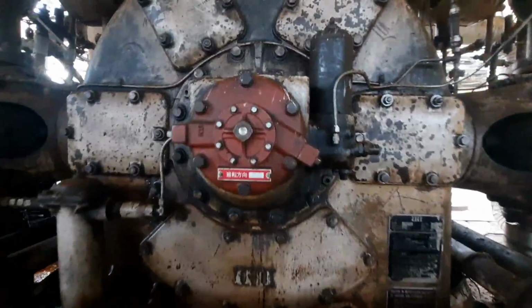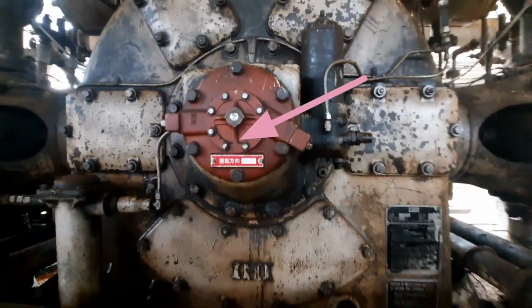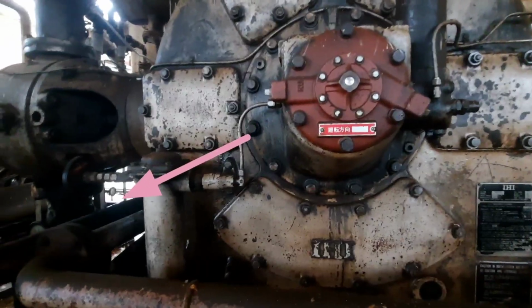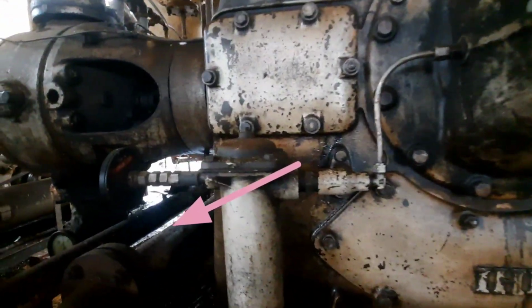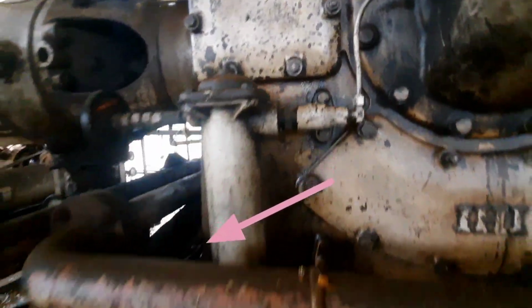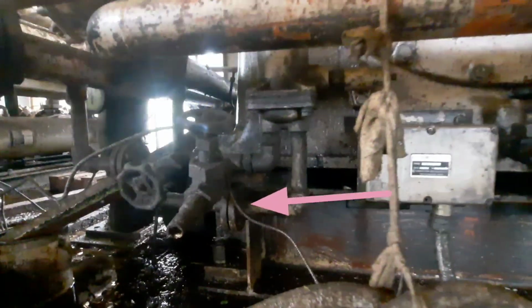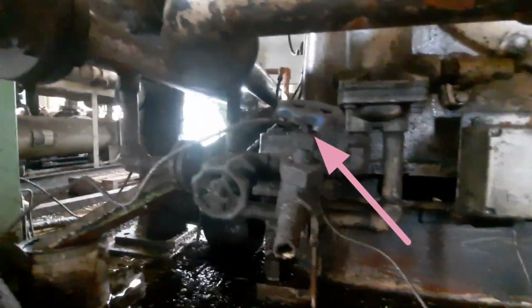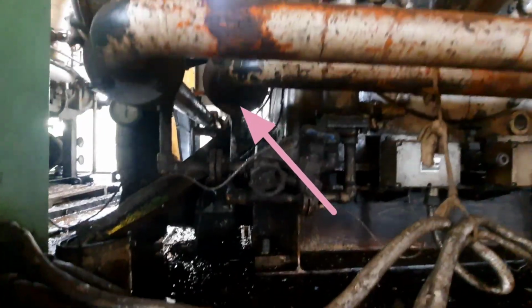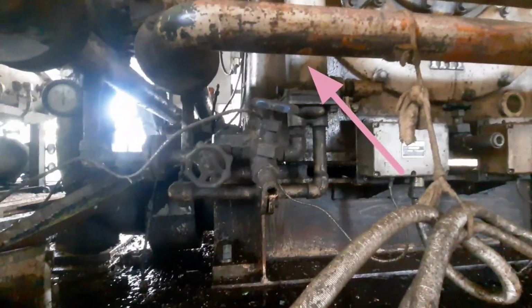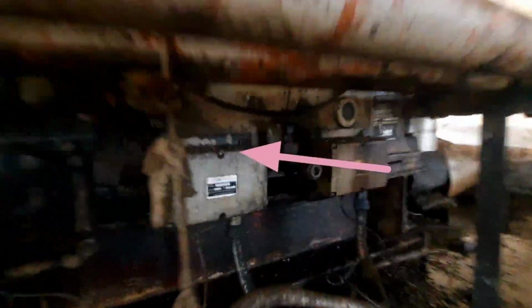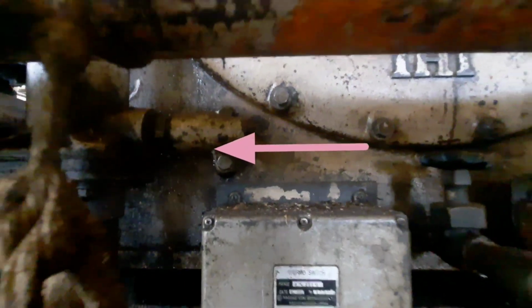So this is the mechanically driven oil pump. On this oil pump, on one side the cooler is available. In the cooler, cooling water is provided. I have already shown you. This cooling water inlet comes this way and another goes as outlet, and it will go to this cooling water main header, and finally it will go to the cooling tower. So one is the inlet line, another is the outlet line.